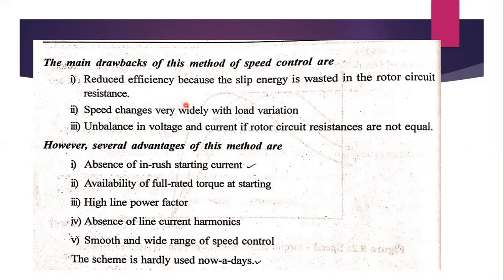That power is wasted in the rotor circuit. This reduces the efficiency because the slip energy is wasted in the rotor circuit resistance. Understood? When the rotor resistance increases, this power loss takes place, and because of that the efficiency of this control method decreases.